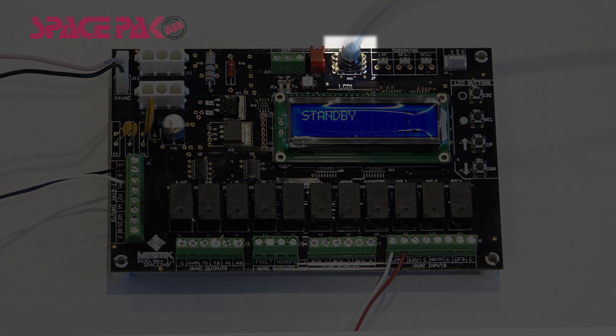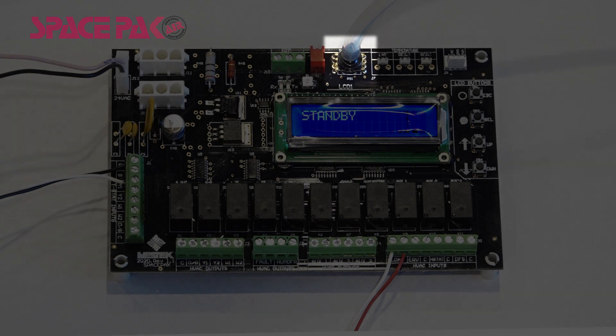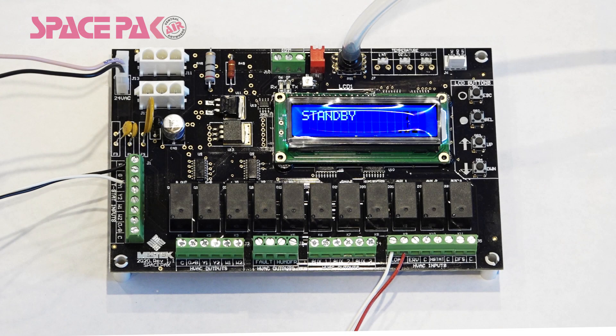The pressure transducer is labeled 'pressure' and will have a clear plastic hose attached to it. This hose is connected to a static pressure tap located at the blower outlet. The pressure transducer reads pressure and displays delivered static pressure on the display screen. The new board has features built in that will allow the installer to use this pressure to balance the delivered air in the SpacePak system automatically. We'll explain this process in the unit settings portion of this video.